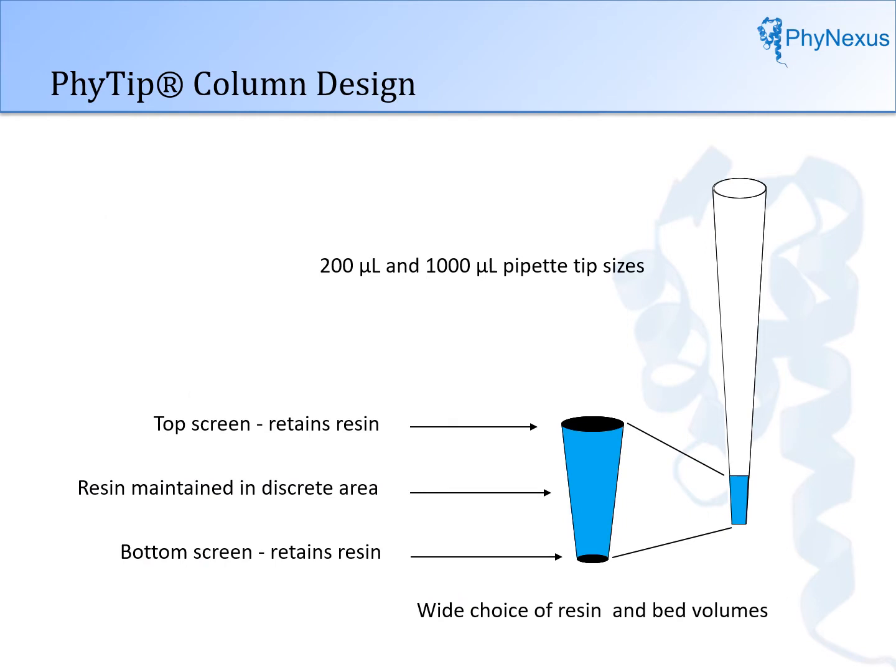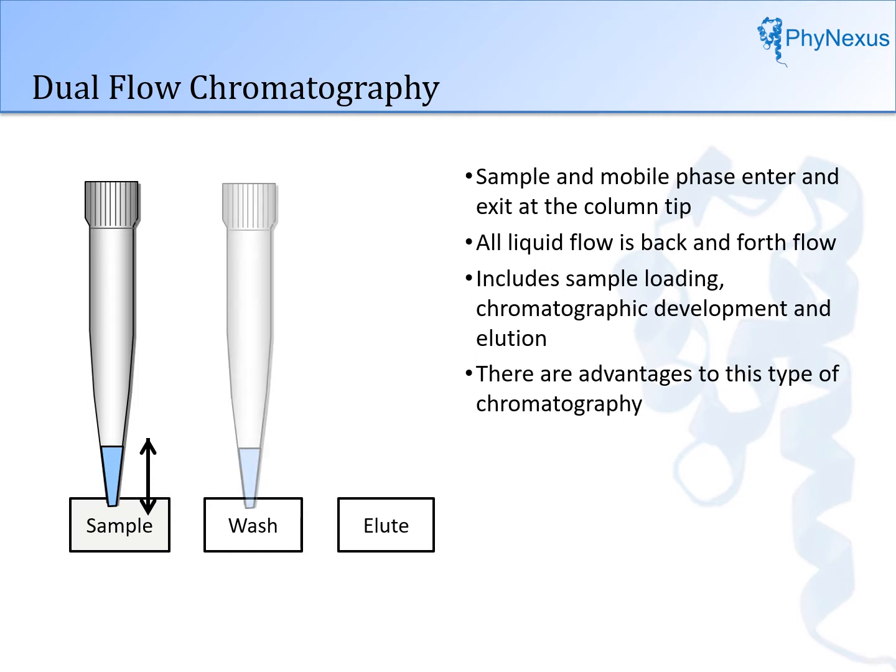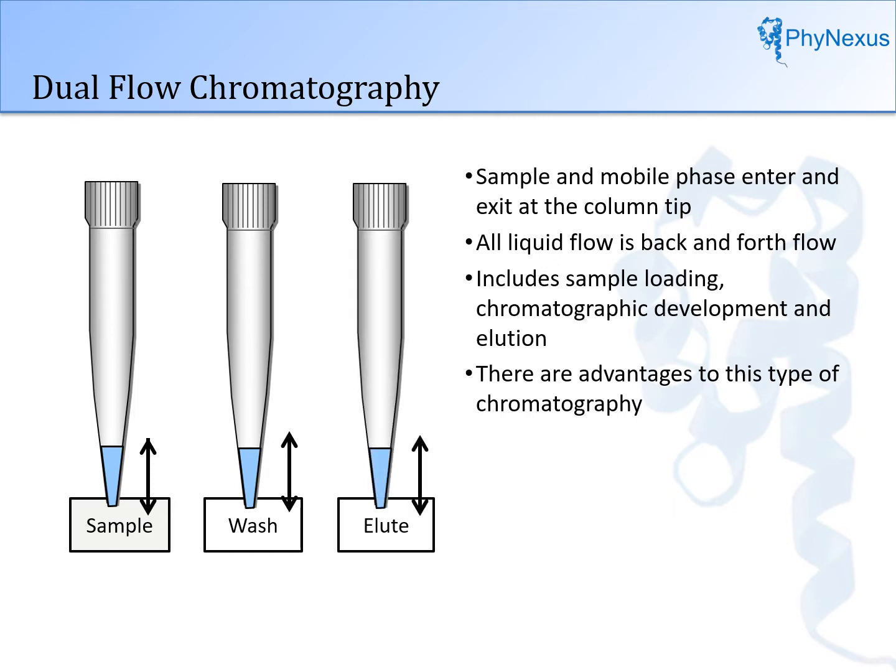To describe the technology, we start with the column. The column bed is located at the end of the pipette tip, contained by a top and bottom screen of woven mesh. The column is available in 200 to 1,000 microliter tip sizes and five different column bed sizes ranging from 5 to 160 microliters. Virtually any type of resin can be packed into the column format. In dual flow chromatography, the sample and mobile phase enter and exit at the column tip — all flow is back and forth. This includes sample loading, column washing to remove impurities, and elution and recovery of the desired material. Hence the name dual flow.